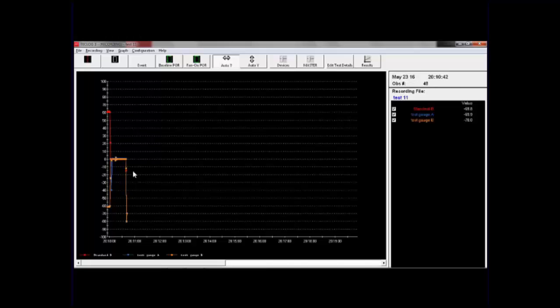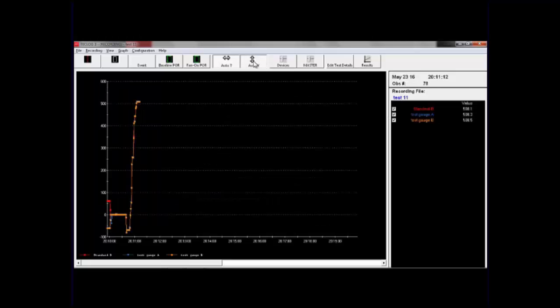And you can see when I connect it to the tubing, it goes negative, and then I am going to pull out to get us up to positive 500. So you can see the numbers changing over here. I'm going to go up to positive, and I want to be 500 plus or minus 30, just in that general range here. So we can see all 3 have gone up, and they're in that range.